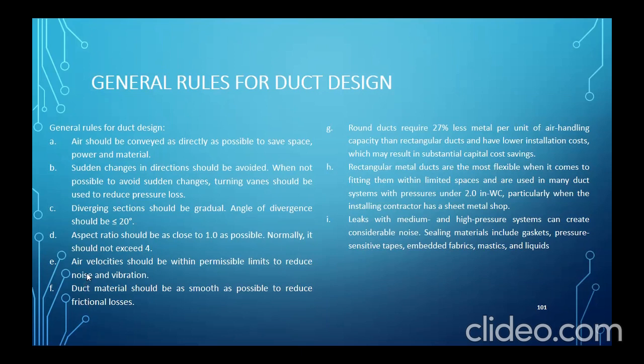E, air velocity should be within permissible limits to reduce noise and vibration. F, duct material should be as smooth as possible to reduce frictional losses. G, round duct requires 27% less metal per unit of air handling capacity than rectangular duct and has lower installation costs, which may result in substantial capital cost savings.